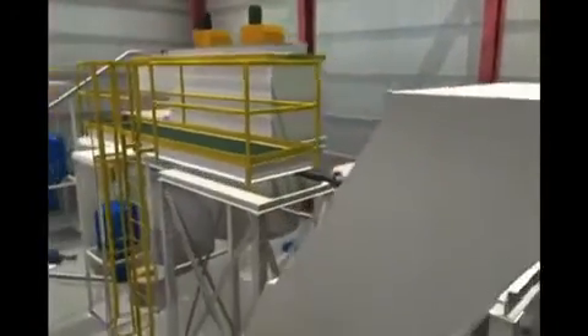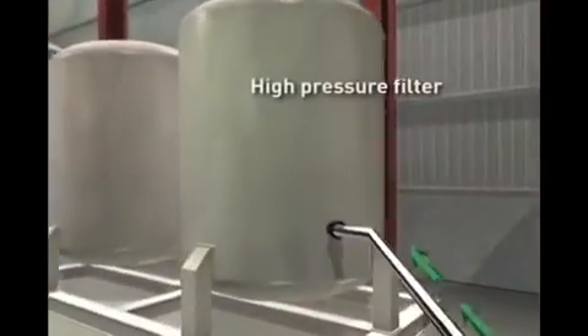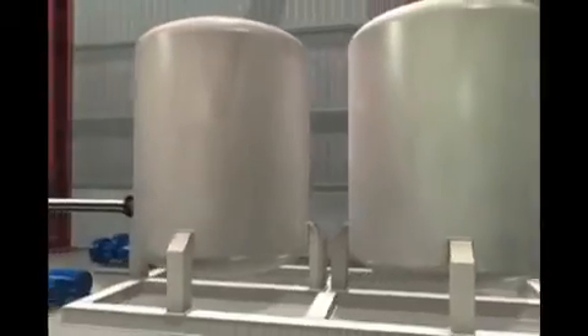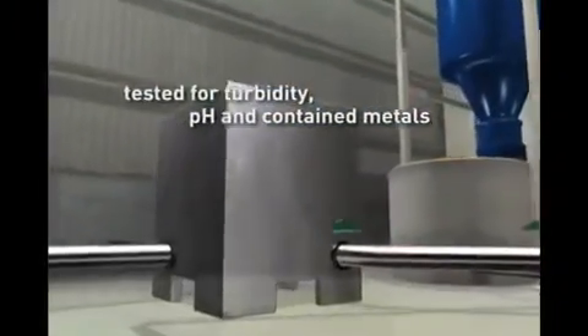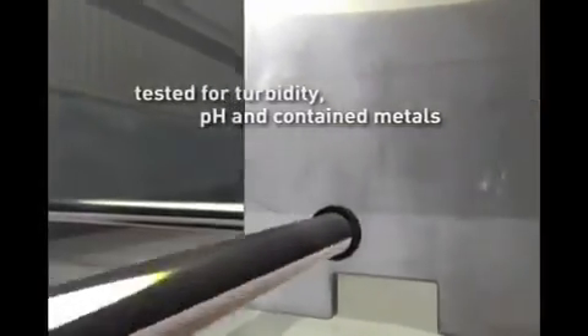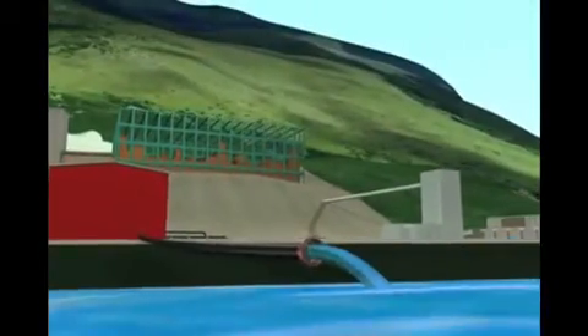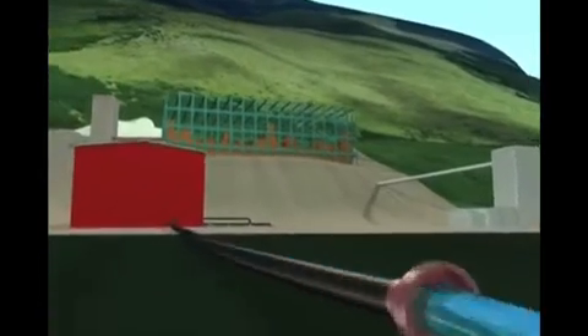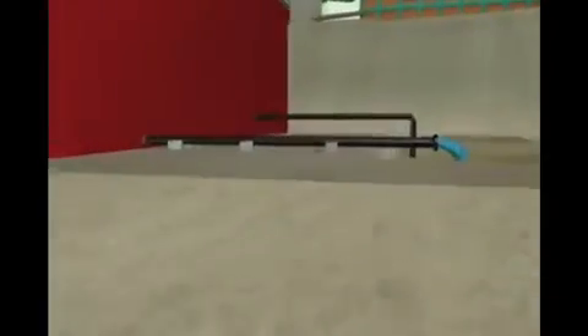It will be included in the paste which will be used to fill the voids of past and future mining. The filtrate is then passed through a high-pressure filter to remove fine suspended solids. The clean water is then tested for turbidity, pH, and contained metals. If it passes the test, it is discharged into the Tulsiqua River. If not, it is discharged back into the site settlement pond and treated again.